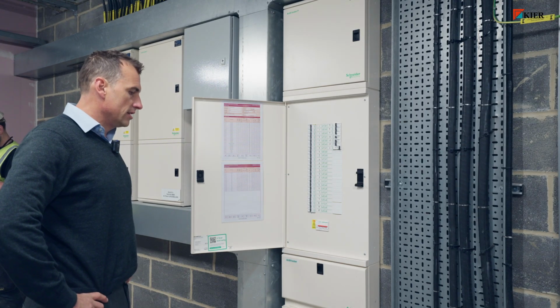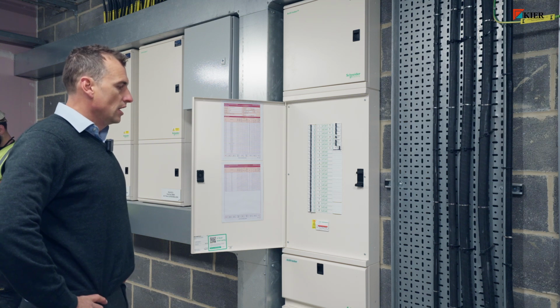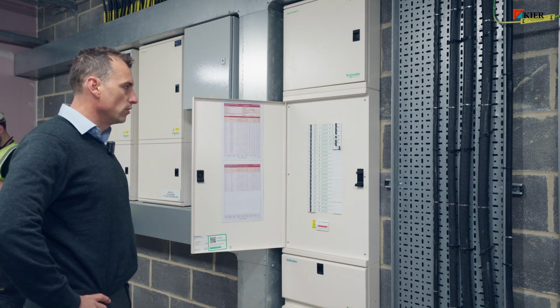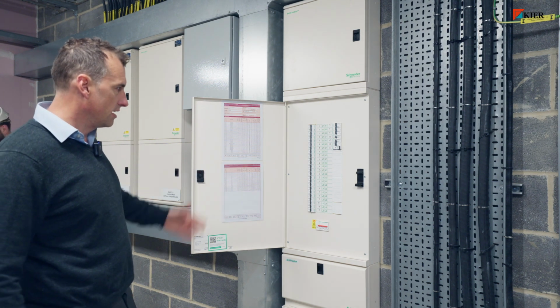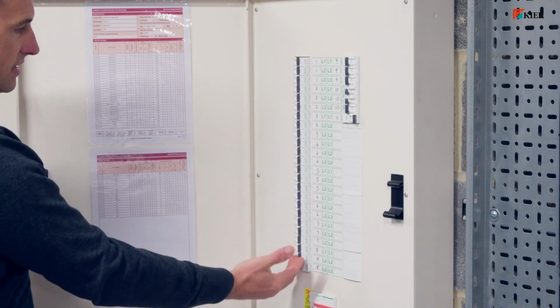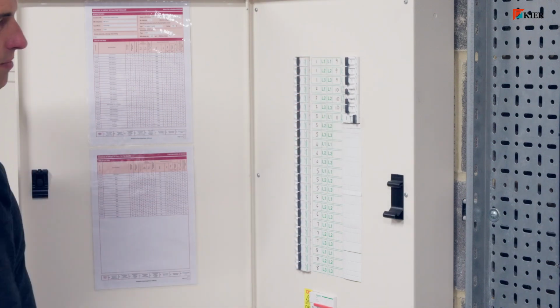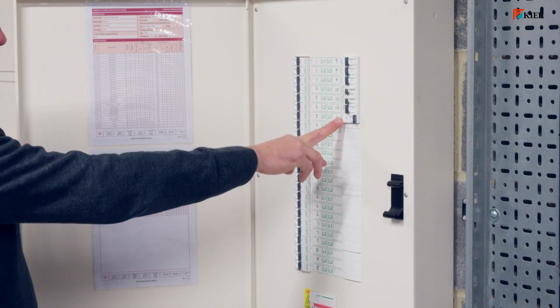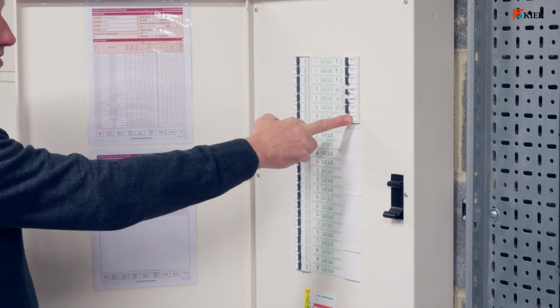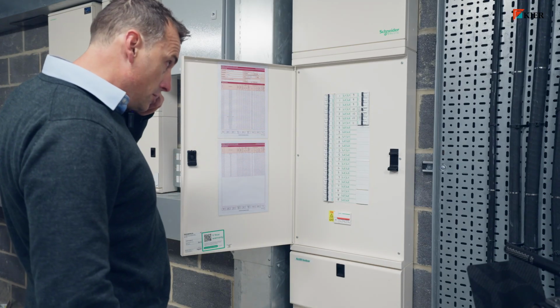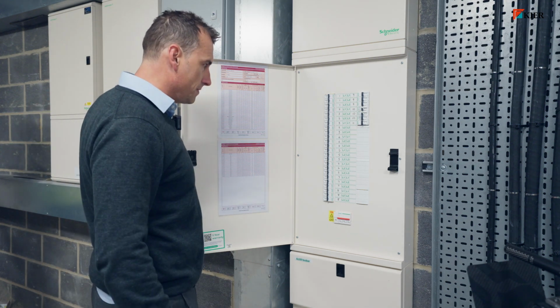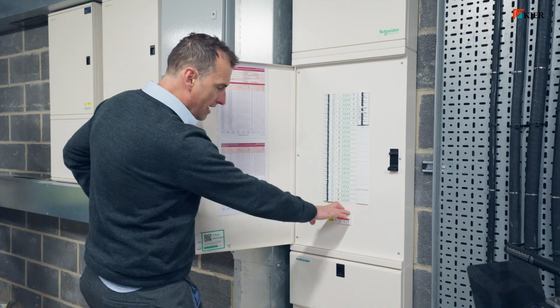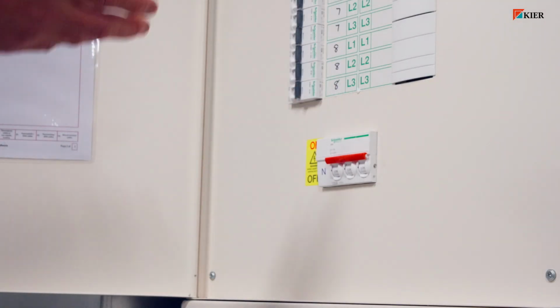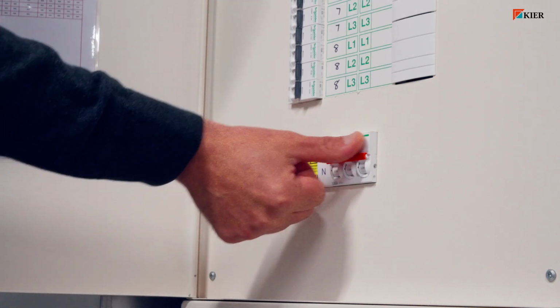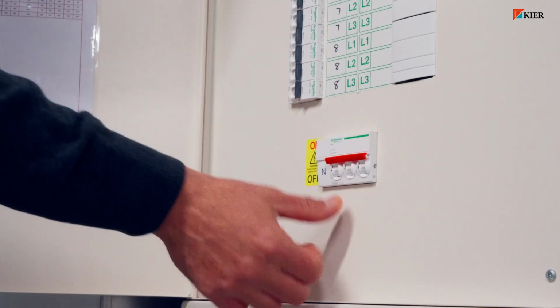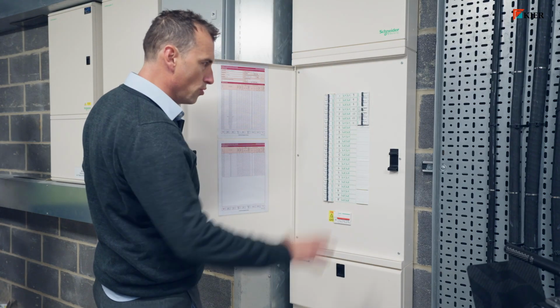So in the event of an electrical circuit tripping through a fault, you would obviously identify and make sure that there is no fault. You would come to the panel, the associated electrical distribution board, look through all the breakers to see which one is inadvertently tripped, locate the tripped breaker, and once you're happy that it's safe to re-energize, it's just a matter of turning it back onto the on position. If any maintenance needs to be carried out on any of the electrical distribution boards, all the distribution boards are fitted with a main isolator. So in order to conduct any works, you'll just go to the main isolator, and you will switch this switch from the on position to the off position, and it will kill all the internal circuitry, so then the board is safe to work on.